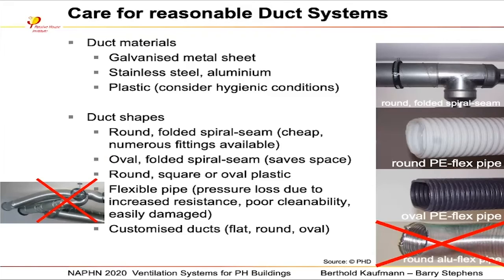Please go for very good ducting, especially smooth ducting. And what is not allowed is these aluminium ducts, which can be very flexible, and this is a problem. The surface on the inside of this duct is very rough, and therefore pressure losses are quite high, so please do not do this. The plastic parts in the middle are rough on the outside, but on the inside the surface is smooth, and therefore it's a good compromise.